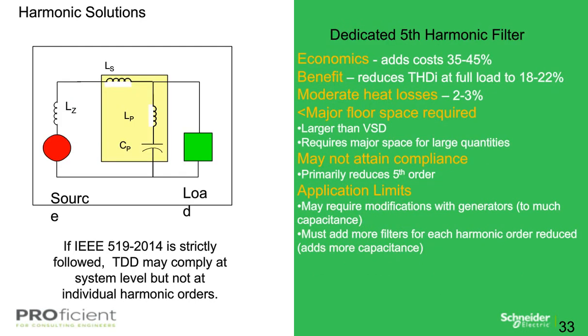So another commonly used harmonic solution would be a dedicated 5th harmonic tuned filter, which greatly would reduce the percent THDI to about 20% with fairly moderate heat losses of 2 to 3%. And this filter can approach or exceed the size of the VFD which they're applied to. So if footprint is an issue, typically this would not be your best solution.